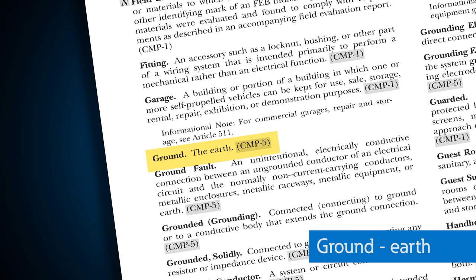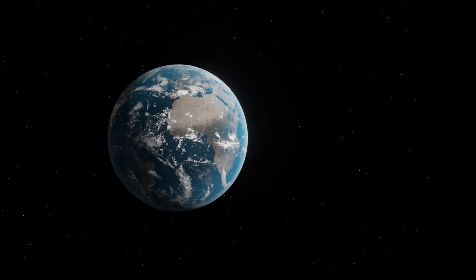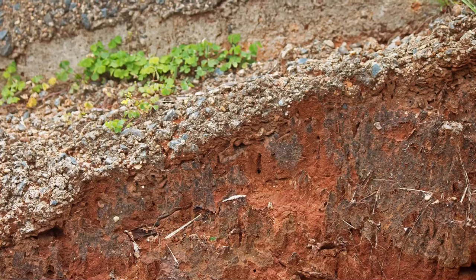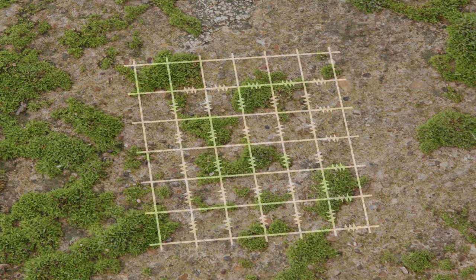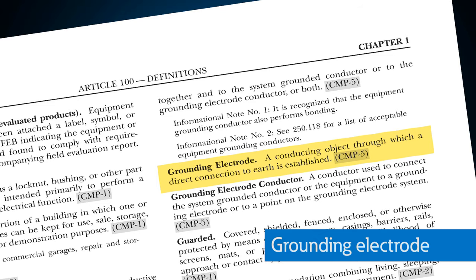The National Electrical Code tells us that ground is the earth — I think it's the shortest definition in the NEC. We define ground as the earth, so anywhere you use the word 'ground' you're thinking of tying to or connecting to the earth. Because the earth does not come with terminals, we have to establish a connection to earth, and we do that through what we call the grounding electrode.